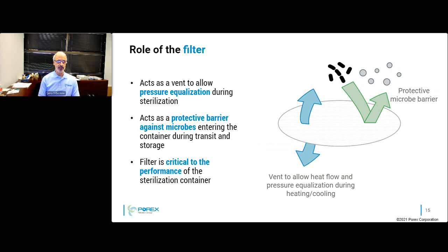It acts as a protective barrier against microbes entering the container during transit and storage. And that's really critical. If you look at the photo on the right, air can pass through, the blue arrow, but the material prevents bacteria, dust, dirt, liquid, water, whatever may condense on top from getting into the container. So it's really critical. Lastly, the filter is critical for the performance of the sterilization container. The container efficiency is only as good as the weakest link, which tends to be the filter. So if you're trying to reduce bacteria or any kind of microbes within your facility, and the paper itself or whatever you're using as the filter has a lower level of bacterial filtration, that bacteria will get into your device.